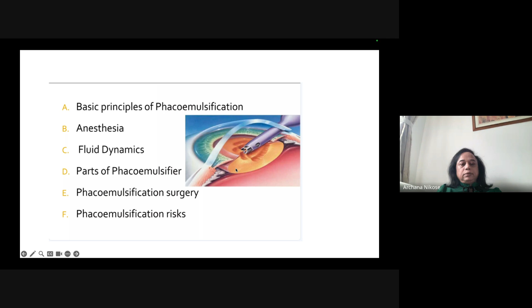Now, these are the parts of the machine. It has an infusion system. That is the irrigation bottle. That's the bottle height, which has a fluid. Then this is the pump, which aspirates. This is the ultrasonic handpiece, and this is the eyeball where this tip will go in. Okay. So it has one irrigation port, which will send the fluid into the eyeball. This has an aspiration port, which will aspirate the emulsified lens, and it will be collected in a bag.